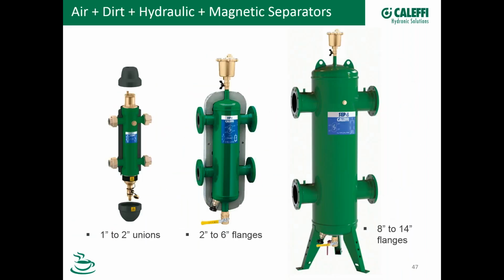So these products, again, we have a full range. The one we showed on the earlier slide is the small one on the left with the union connections, and that comes in sweat, threaded, or press. So the tail pieces give you good flexibility there. It comes with that insulation jacket with the top and bottom piece and the front piece to cover it all up. And the one in the middle, the 2-inch to 4-inch, also comes with pre-molded insulation jackets.